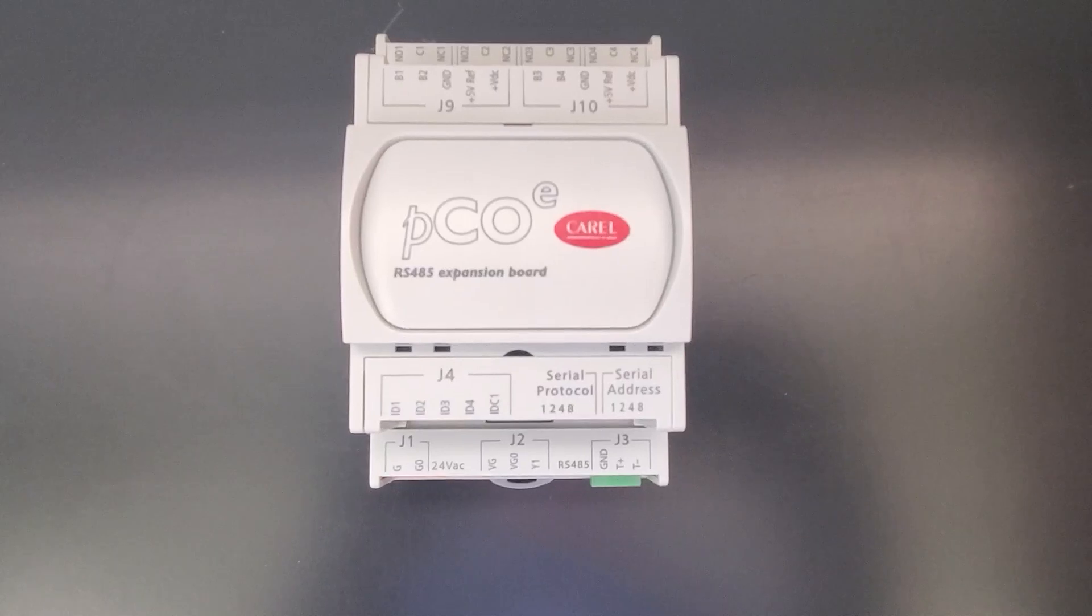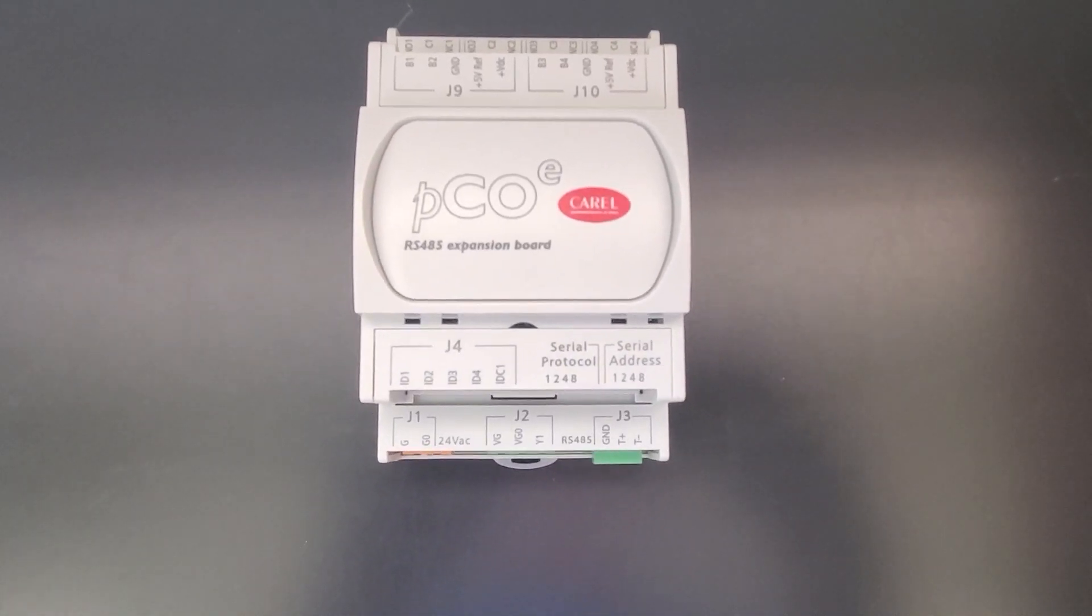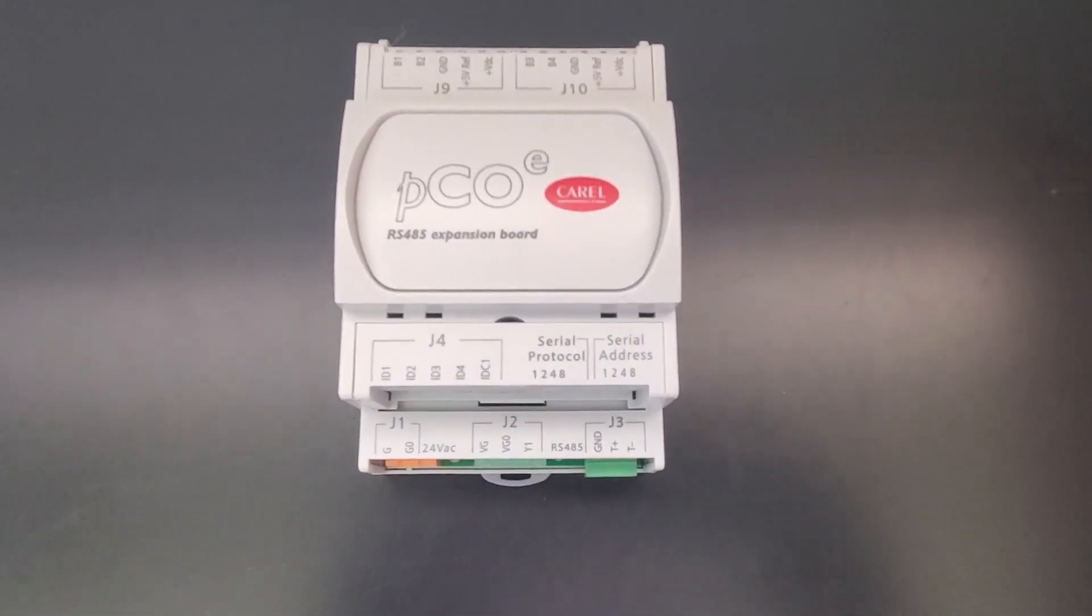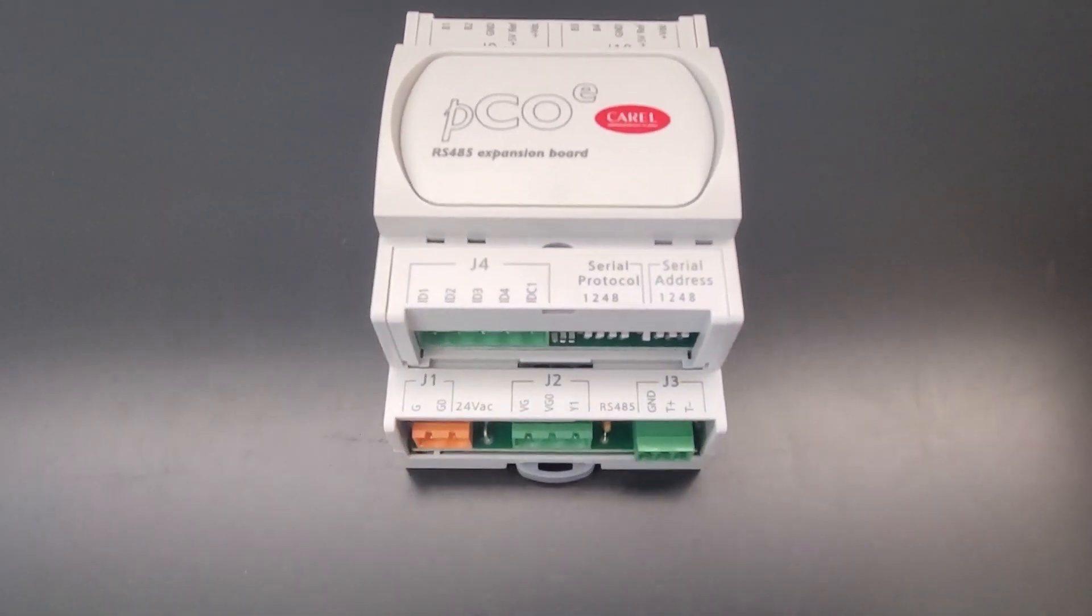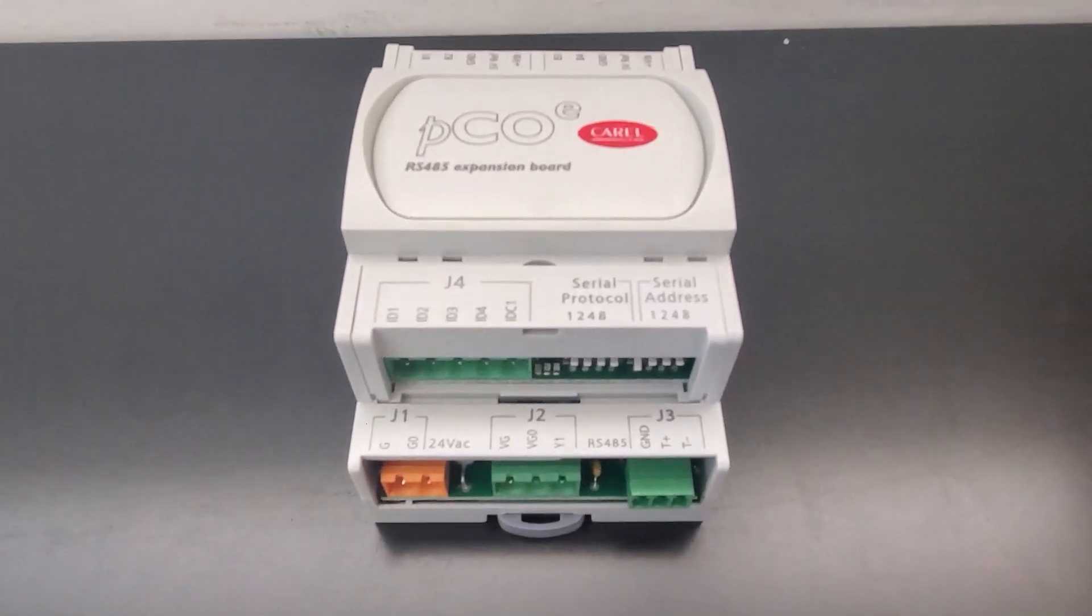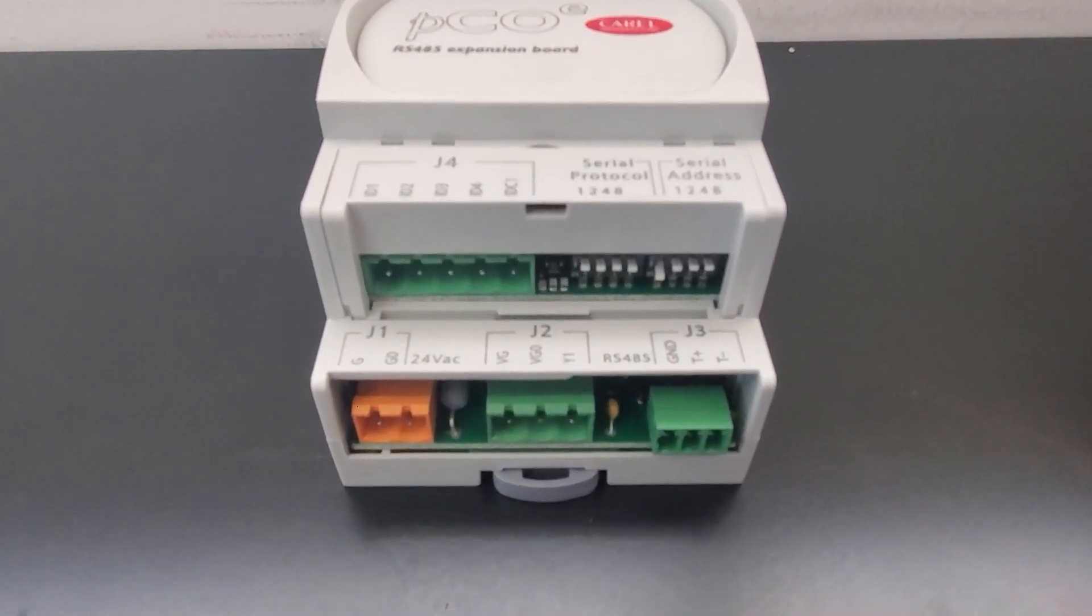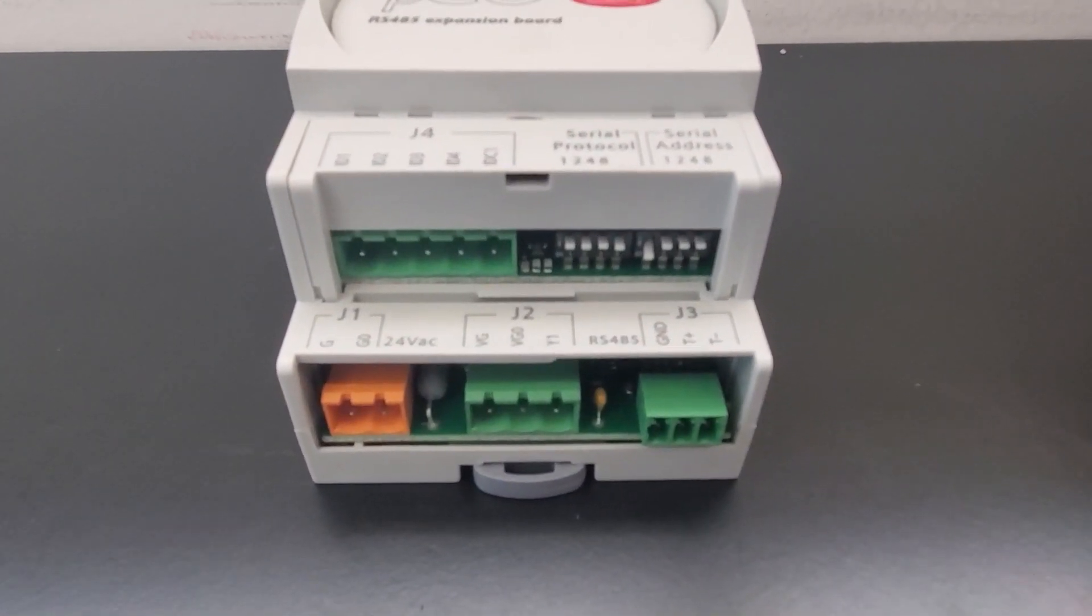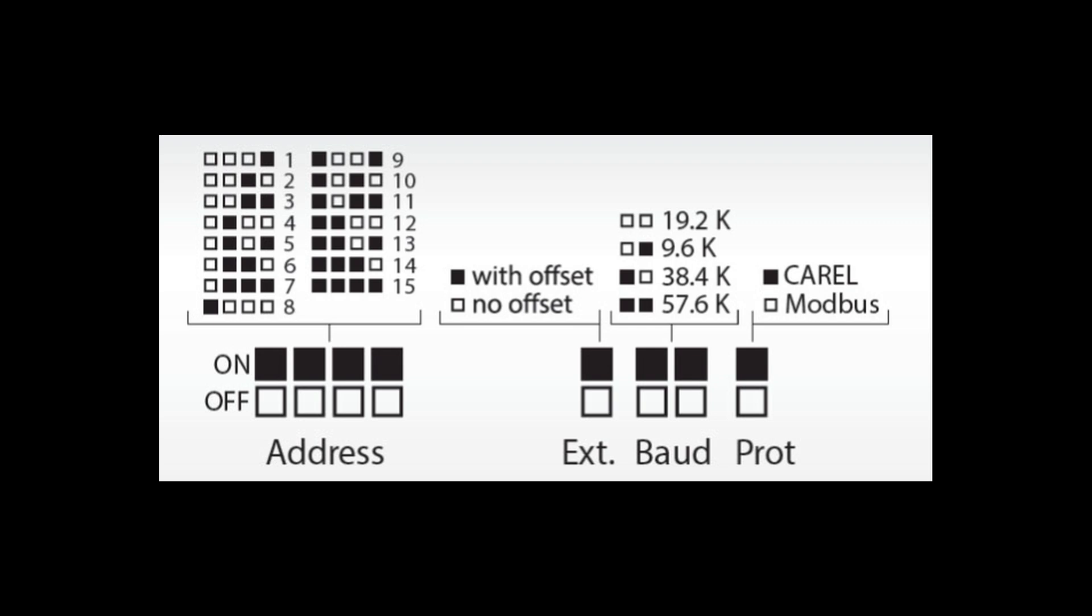If you are replacing a small pCO e instead, you will need to address it using the dip switches. These are located at the lower edge of the board where it says serial address. Use this chart to determine the position of the switches. Note the black boxes indicate the switch should be in the down position.